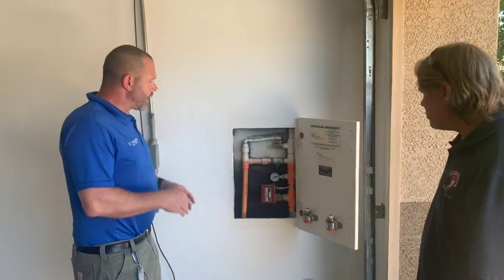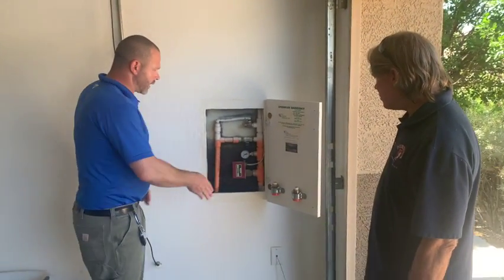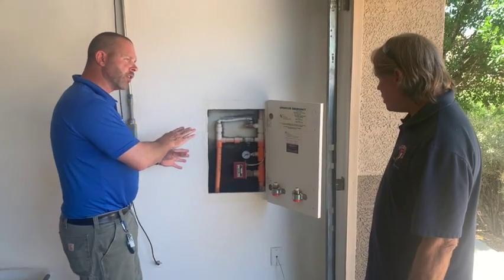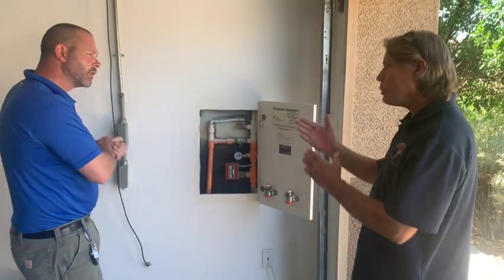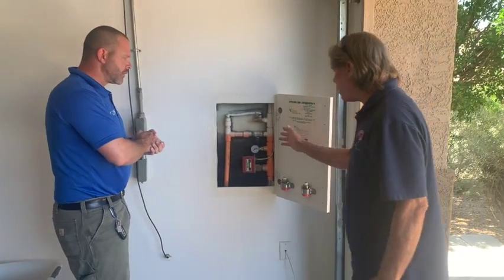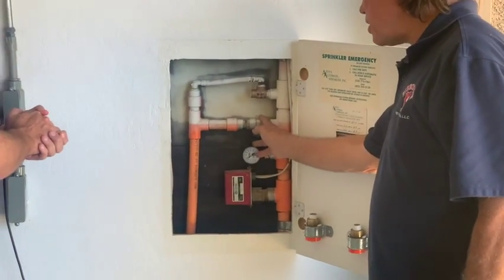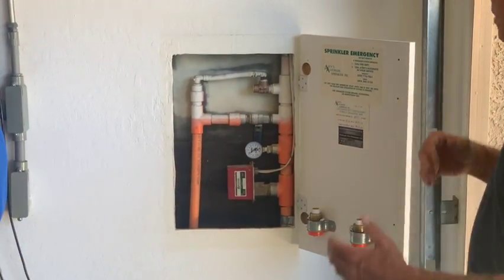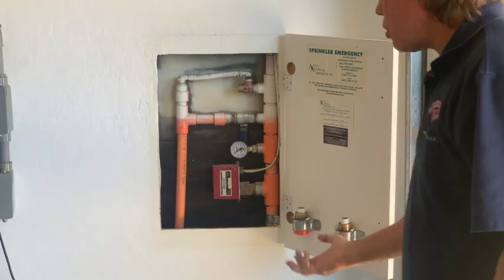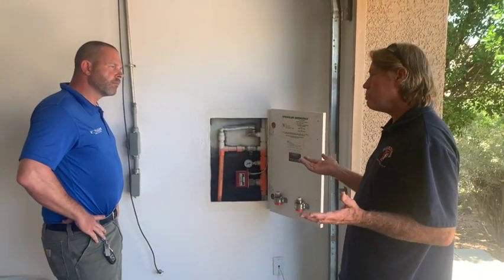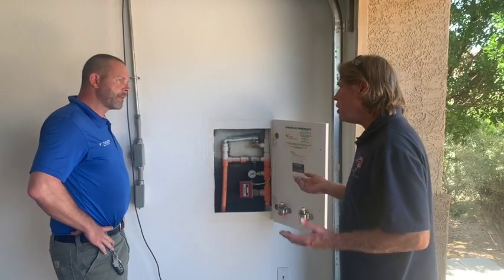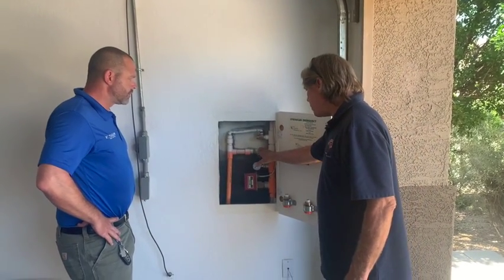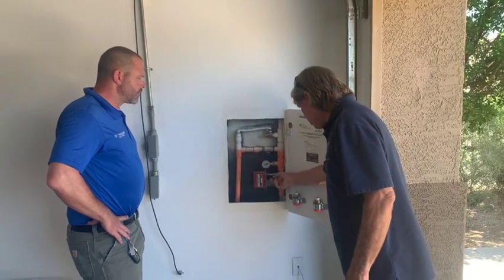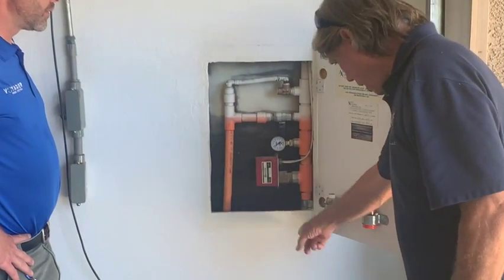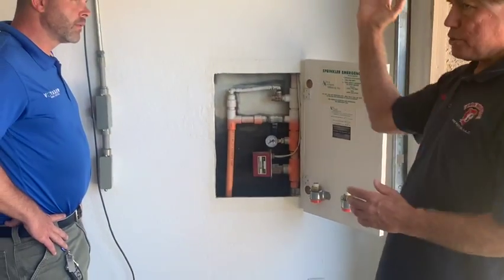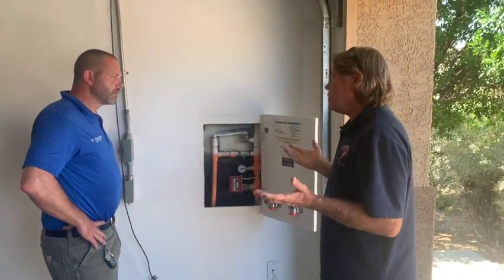Now, earlier you were talking about operating the valves to make sure that they work. Is this one of those valves that you operate, or do you leave this one alone for the professionals? Actually, that is correct. I would prefer that you not operate this valve, not because you shouldn't, and not because it shouldn't be operational, but in many cases it's been sitting for years and years, and as long as it's not leaking out there, I don't want to see people cause a problem for themselves and cost extra money. So you really don't need to operate this valve. The only thing this is going to do is ring the bell by way of the flow switch. It's going to operate that check valve, but all of the rest of the trapped water in the system isn't going to get flushed out.